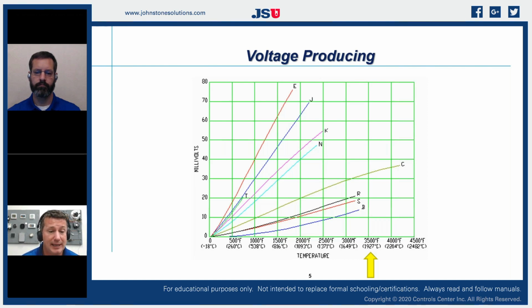You know, a lot of us are familiar with the K-type thermocouple, right? That's the one that we still use today in our digital multimeters. That's the K one. It's only good for 2,500 Fahrenheit. Most of the time, I'm not working on something 2,500 degrees Fahrenheit with my thermocouple. It's got plastic tips and handles and leads on it, right? But I can do that with my C-type, my thermocouple that I use for furnaces and for boilers and most of our heating appliances. So at 3,500 degrees Fahrenheit, I can produce 30 millivolts with that C-style thermocouple.